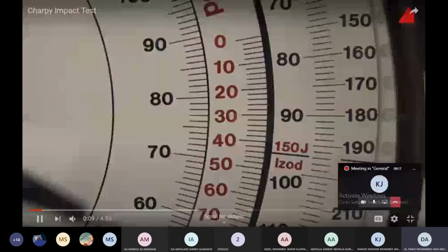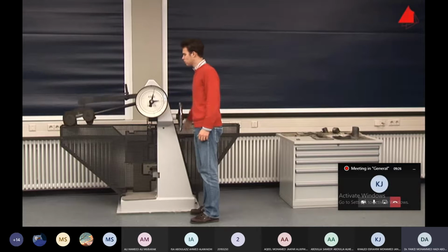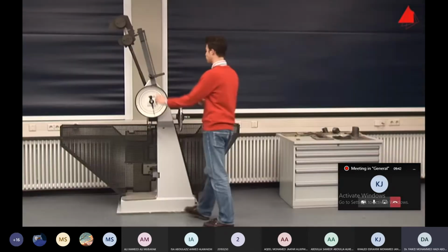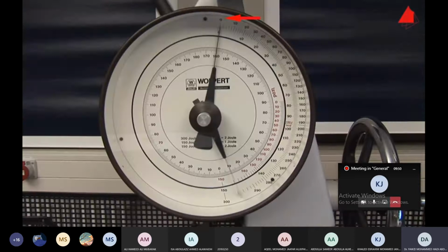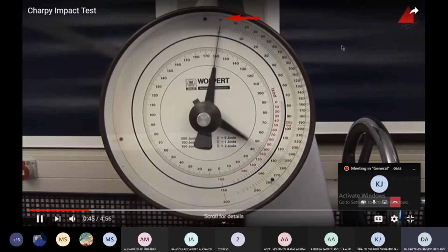Has been designed to measure the toughness of materials under impact loading and multi-axial stress state. A pendulum impact testing machine is used to do so. The pendulum on the machine has a heavy weight at the end. This is lifted into the starting position in step 1. Then the tester checks whether the testing machine has been adjusted accurately. In order to do this, he turns the drag indicator downwards and releases the pendulum without a test specimen. The drag indicator stops at position 0. This proves that the pendulum has the correct starting position and that the friction is correctly compensated.